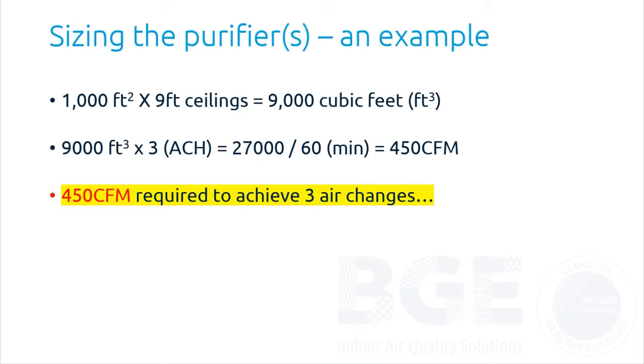You have a 1,000 square foot room with 9-foot ceilings. That would be 9,000 cubic feet of air in that space. You take the 9,000 cubic feet, and you're looking for 3 air changes from the room air cleaner, which is 27,000 cubic feet divided by 60 minutes. So you're looking for 450 CFM to get those 3 air changes.